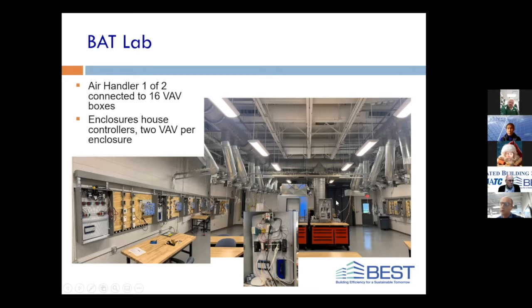Outdoors we have 2 chillers, 1 dedicated to each air handler, and we're procuring a single boiler for both. We've got preheat and reheat on one air handler, electric preheat and hydronic reheat on the second, and hydronic reheat on all the VAV boxes. So there's going to be a lot of demand for our water, and we're working hard designing that.